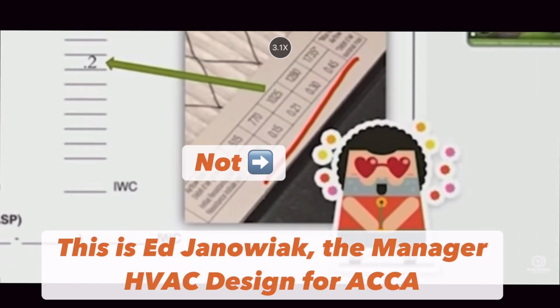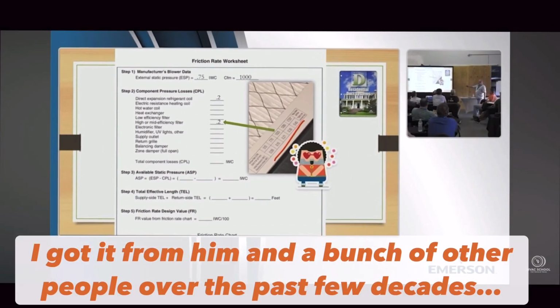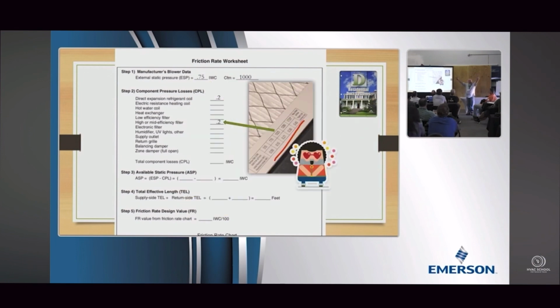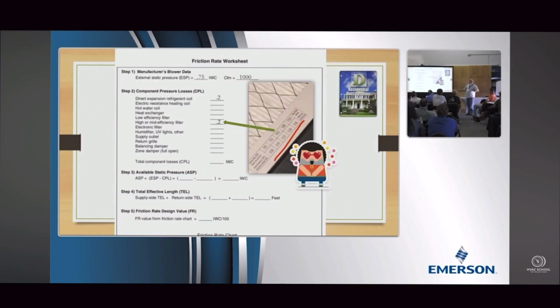Filters are next. This is my favorite slide because it shows the pressure drop info. I love that. When I become king someday, I will require every filter manufacturer to publish that right on the filter—no looking it up, no math. They're telling us that if I'm moving 1,000 CFM, I'm going to have a 0.21 drop.